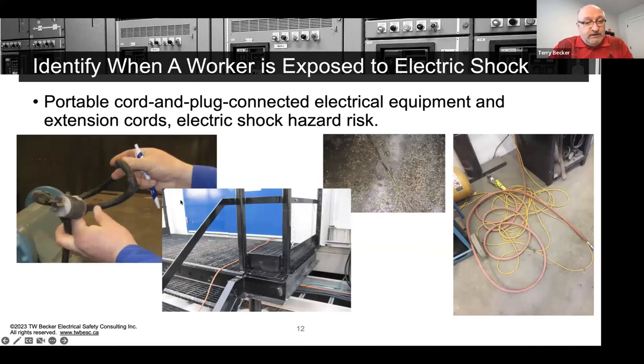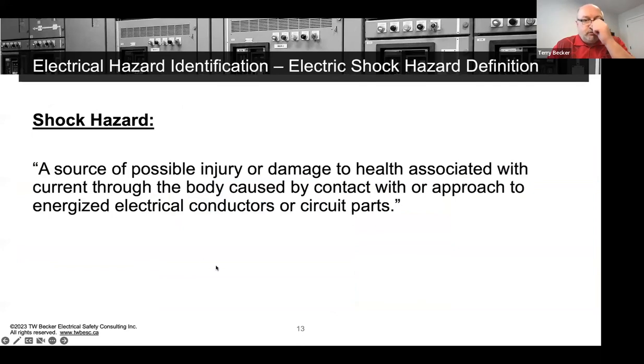a shock risk assessment. So I've got some pictures here because I have to do this every time. We need to manage portable cord and plug connected electrical equipment for its condition. And electrician's tape is not allowed to be used by any worker other than really an electrician, right? But forever, you're going to see this on job sites. The worker damages it, they have tape, they tape it up. So they need to basically tag it and bag it, give it to the supervisor and be provided a new one. And then an electrician would repair it if they can and put it back into service. So I emphasize this all the time. We've got to make sure we manage that.